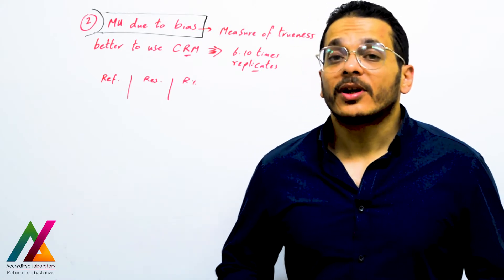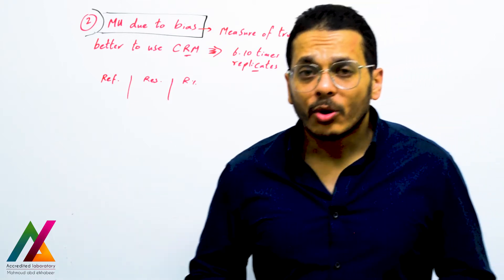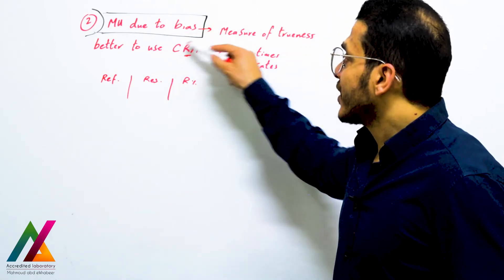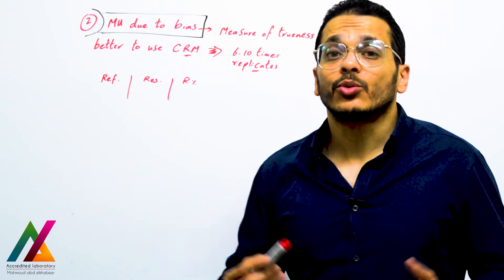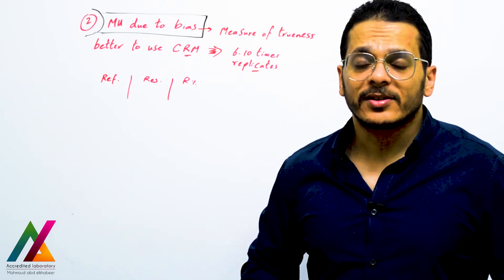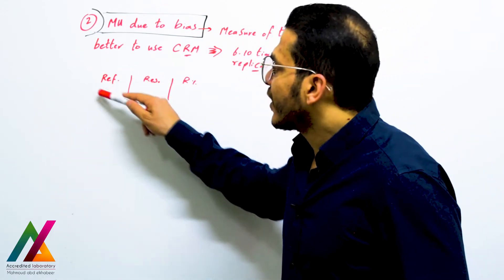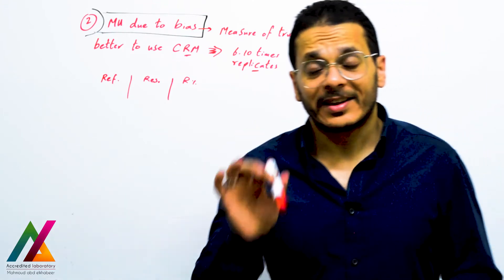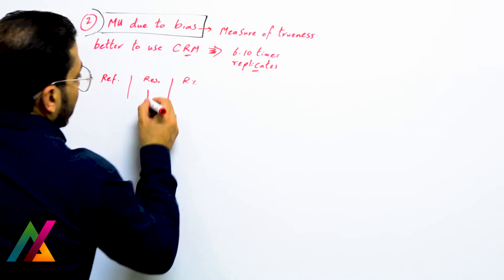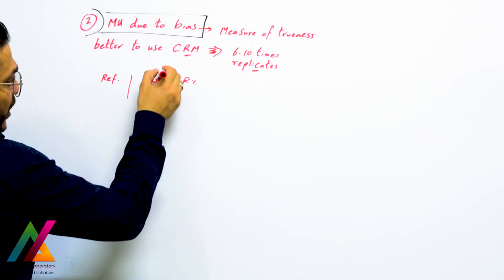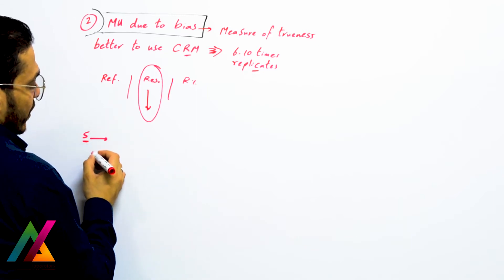After that, you calculate measurement uncertainty due to bias from trueness evaluation. It is best to use a certified reference material (CRM) that contains your target analytes. You should analyze 6 to 10 replicates of this CRM, and you have the reference value for your target analyte from the CRM certificate.